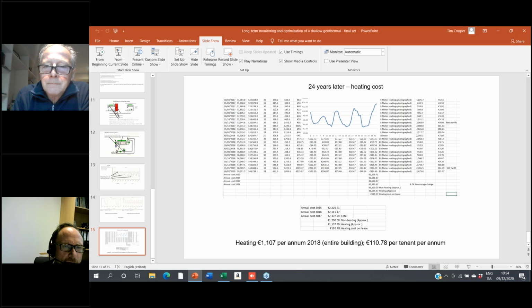I have another question, maybe just to totally understand the concept. So you have one well extracting the energy for your building. Is it a one well solution? It's a single borehole, a single well, drilled down 170 meters. We pull the water out of the top of the well, 2 meters below the water table, pass it through the heat pump, and return the chilled water to the bottom of the well in a plastic pipe that drops down inside the well. The water then migrates up in contact with the limestone to the top, extracting heat as it goes.